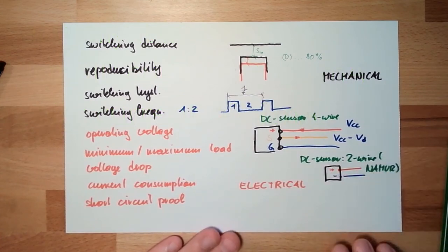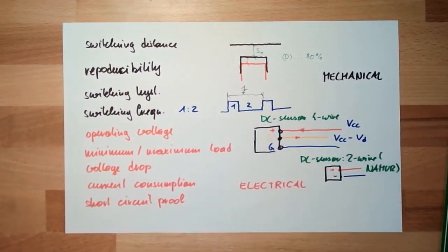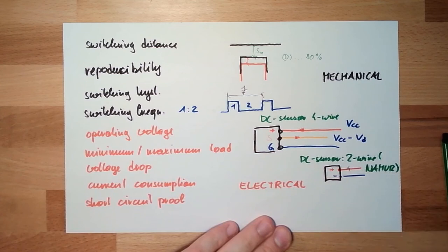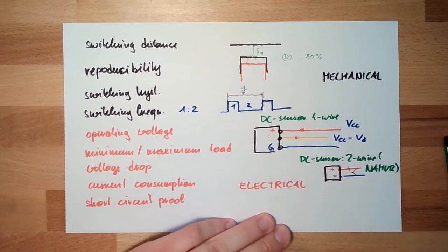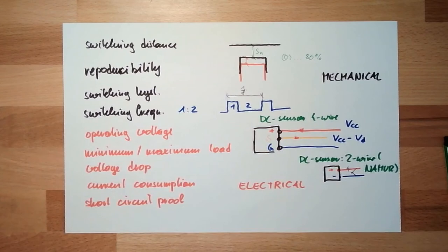Then you have a special analyzing tool. You can't just put a load on it, like a relay or something else. In NAMUR, you have some Auswertegerät, some evaluation unit in English. You need it, and this evaluation unit is then making contact or not. However, these things can watch themselves. Since there are two types of current, a wire break can be analyzed, and even a short circuit can be analyzed, because then it's too much current. So those things have benefits.